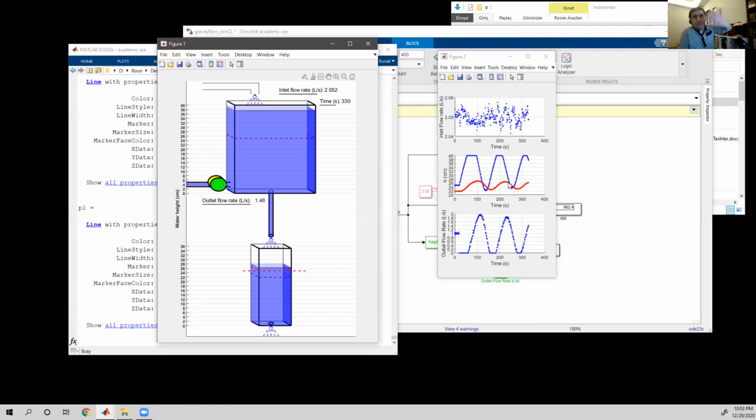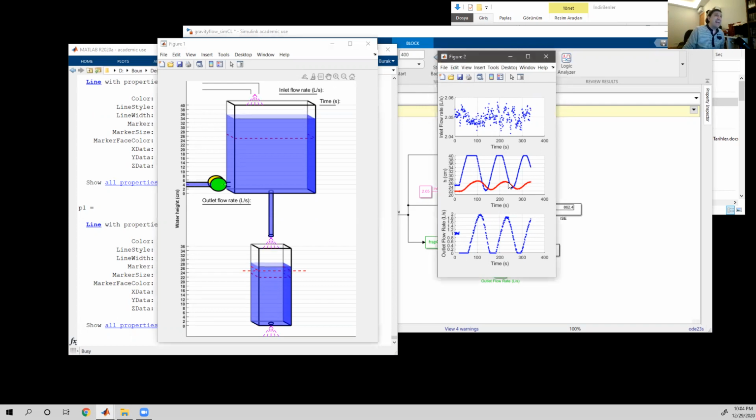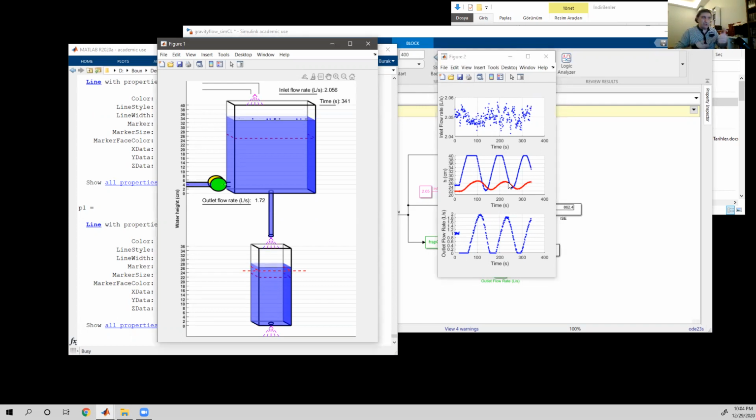Otherwise, the manipulated variable would not know whether to close or to open in the presence of a positive or negative error. But if you don't know about this topic, you should really think about it to understand it more thoroughly. It's not a very straightforward concept. And this negative and positive sign is usually known in industry as direct or inverse action. It is also an important concept here.